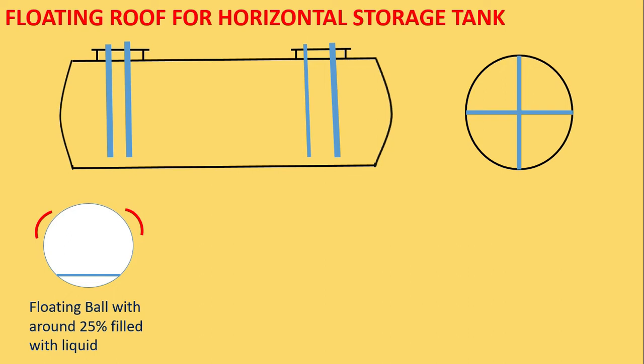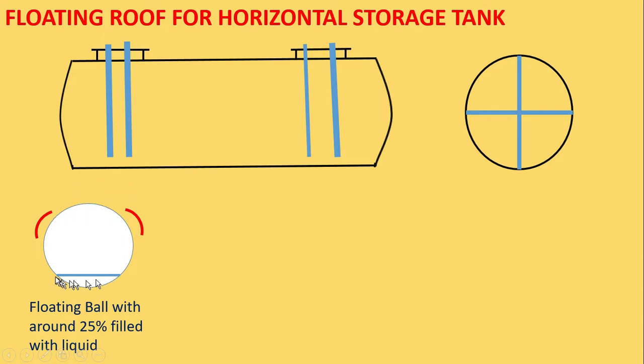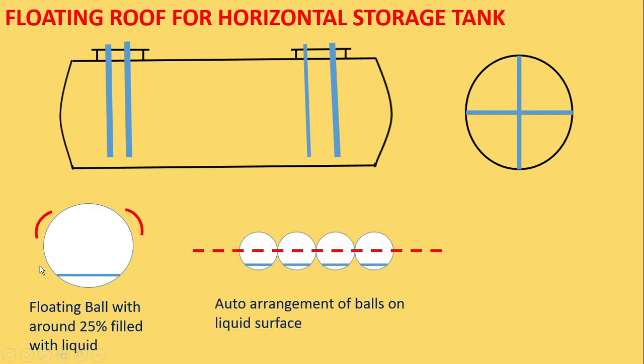The purpose of having the weight at the bottom is to avoid clockwise or anticlockwise rotation. If the ball rotates and an unweighted area rises to the top, the PMS attached to that area will evaporate very fast, which is restricted by the weight on one side. Once we place such balls inside the tank, they will automatically adjust due to buoyancy force and will get arranged around the poles, various pipes, and stiffeners inside the tank.